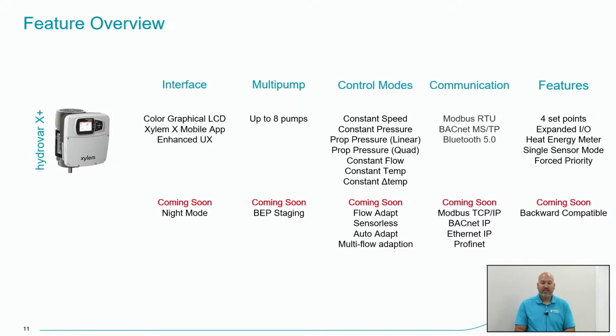All right, moving on to some other features. There is a color graphical LCD display on the unit. You can download the Xylem X mobile application, which is basically a handheld screen for you to use. We'll touch on that in more detail later in the presentation. You can do multi-pump applications up to 8 pumps without the need for an external PLC. There are a bunch of different control modes, ranging from constant speed, constant pressure, proportional pressure, and linear or quadratic, to constant flow, constant temperature, differential temperature, and differential pressure.